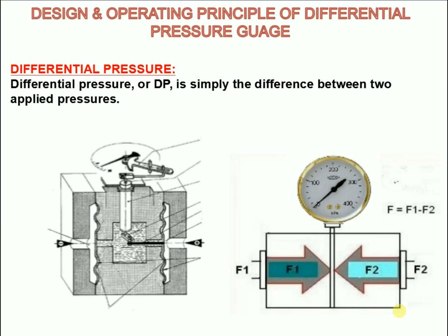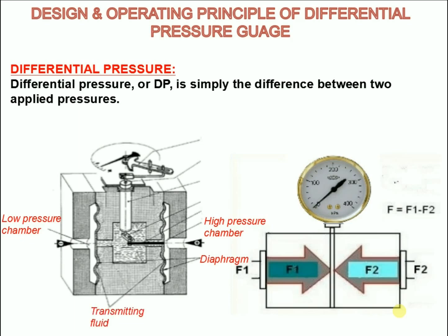Now we will see the operation of the differential pressure gauge. When process pressures are applied to the low pressure chamber and high pressure chamber, the area between the two diaphragms is filled with a transmitting fluid. Any pressure differential will deflect the diaphragm, and the deflection is hydraulically transmitted to the other diaphragm by the transmitting fluid. The deflection of the diaphragm is transmitted to the pointer by means of a rotating axle that provides frictionless transmission and a metal-to-metal seal with the help of links.